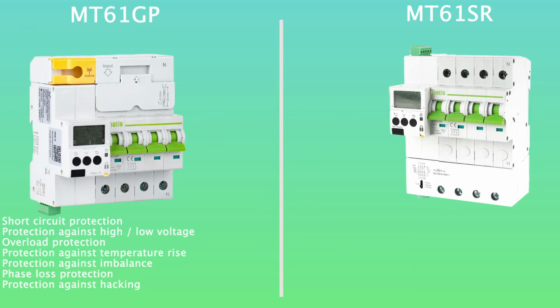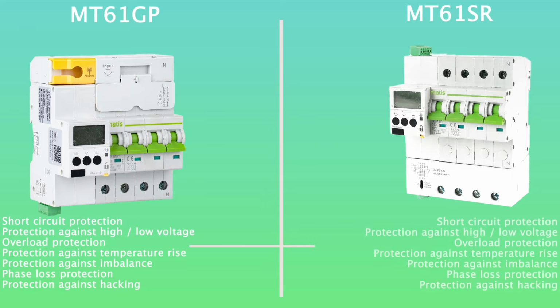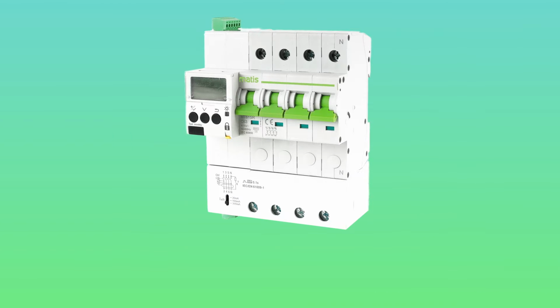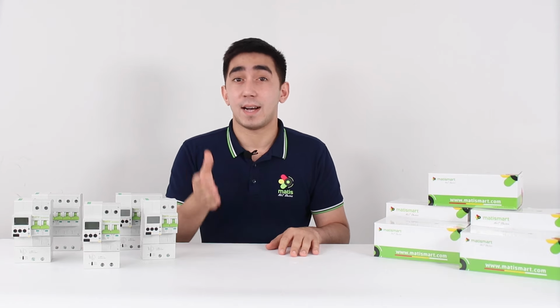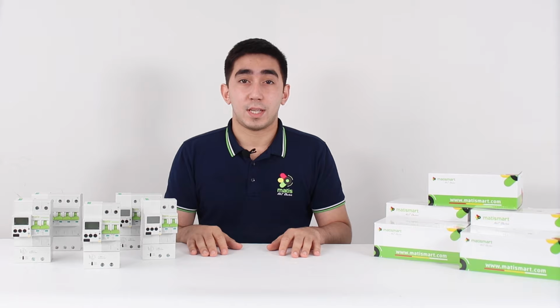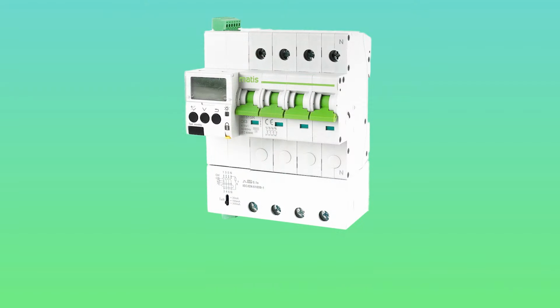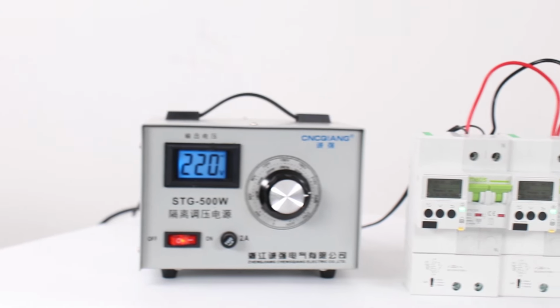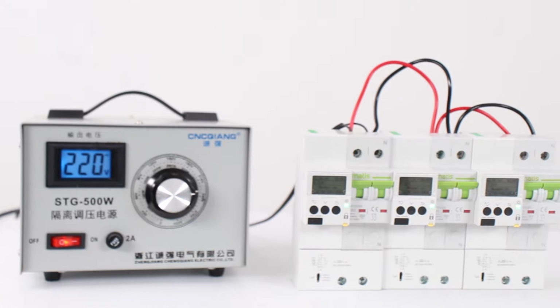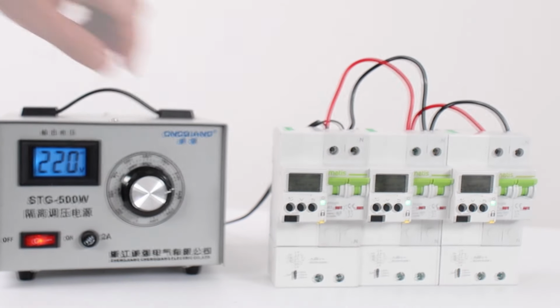It includes all the protective functions of the MT61, as well as protection against residual current. Simply put, this is a differential circuit breaker, or as they are often called, RCBO. However, unlike traditional RCBOs, MT61SR additionally provides protection against phase loss and protection against high and low voltage. Let's see in practice how this protection function works. We have connected the devices to a voltage converter and will test it under the influence of high and low voltage.